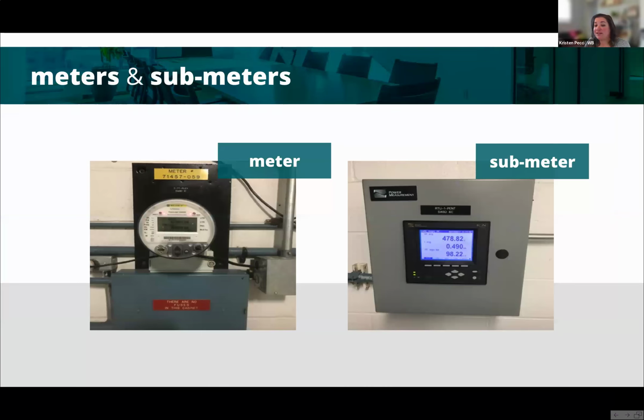And so we have talked specifically about submeters. There are different types of electrical meters. Here you can see the two different types. On the left is what we refer to as just a meter. It's installed by a utility company, and it's usually used by that utility company to bill consumers for incoming electrical service. These utility meters typically have a CT, or current transformer, cabinet, which you can see in this photo below the meter. And it's usually locked by the utility. The only one who has access to either the CT or the meter itself is the utility company.